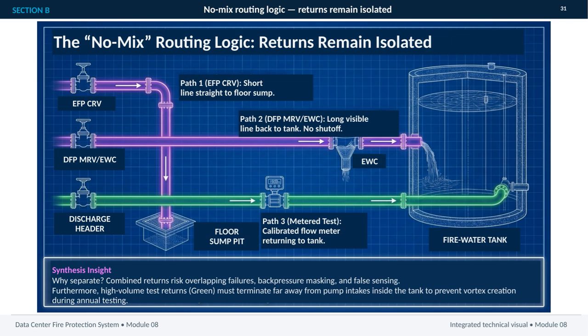It passes through a calibrated flow meter before returning to the tank. This separation is important because combined returns could create overlapping failures, mask back pressure, or produce false sensing. The diagram also highlights a specific requirement for high-volume test returns, shown in green. Those returns must terminate well away from the pump intakes inside the tank. The purpose is to prevent vortex creation during annual testing, which could interfere with reliable system operation.